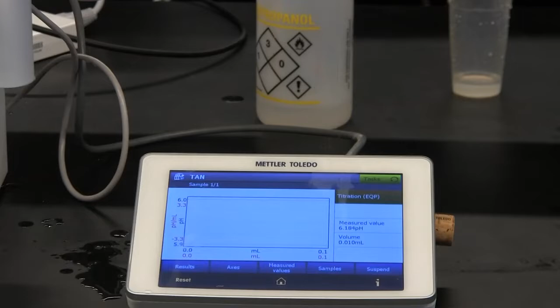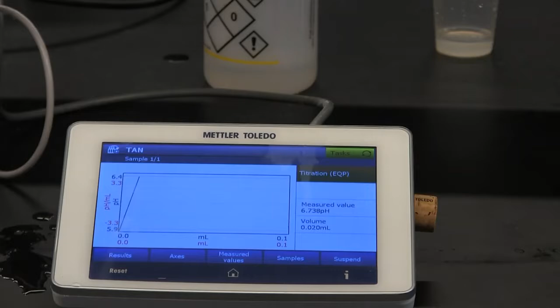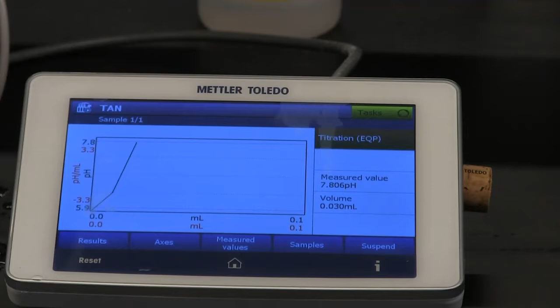Then it will start measuring, showing you the curve of the measurement until it finds an inflection point, which is your acid number. If you miss your inflection point, that means you added less oil than you should have, so you increase the volume of the crude oil. If you added 10 grams and you still missed the inflection point, you then add 20 grams and repeat.